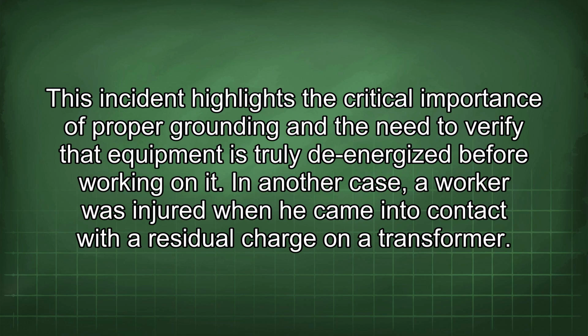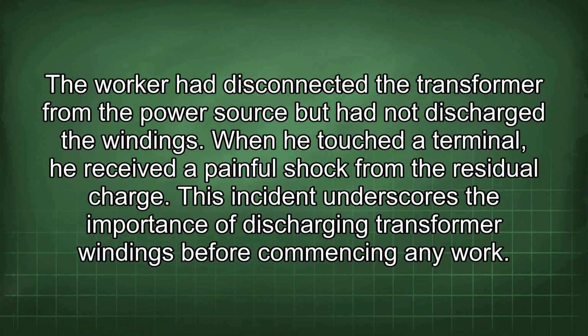In another case, a worker was injured when he came into contact with a residual charge on a transformer. The worker had disconnected the transformer from the power source but had not discharged the windings. When he touched the terminal, he received a painful shock from the residual charge. This incident underscores the importance of discharging transformer windings before commencing any work.